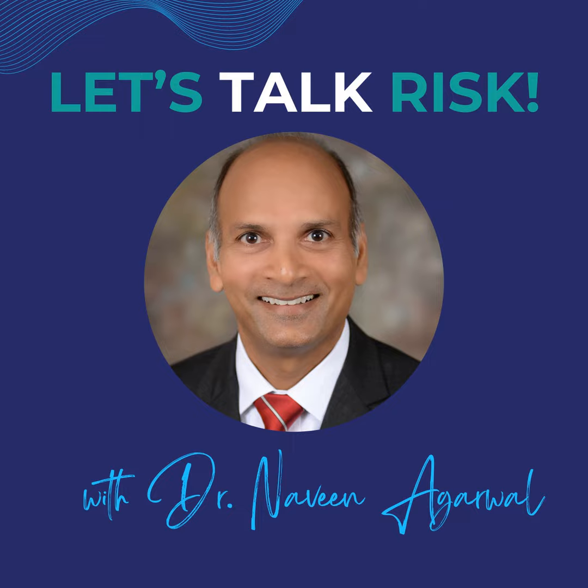So I think the two purposes of it, though, is one, it needs to drive your human factors work. And the other purpose for it is to inform your risk. And I think sometimes it can be a challenge when people try to use it for both without acknowledging that it's needed for two different reasons. Right. It's needed to go drive your human factors activities, which then come back and help you inform your risk. And so thinking of it as an interwoven process, and that document, specifically the URRA, has multiple audiences, right?